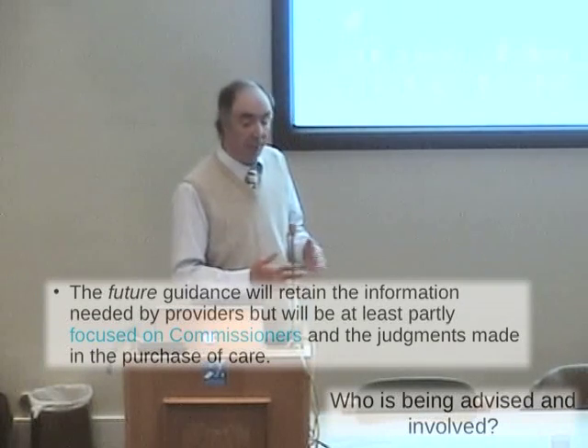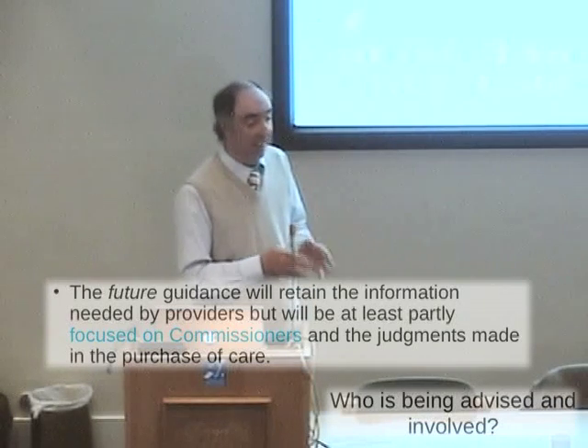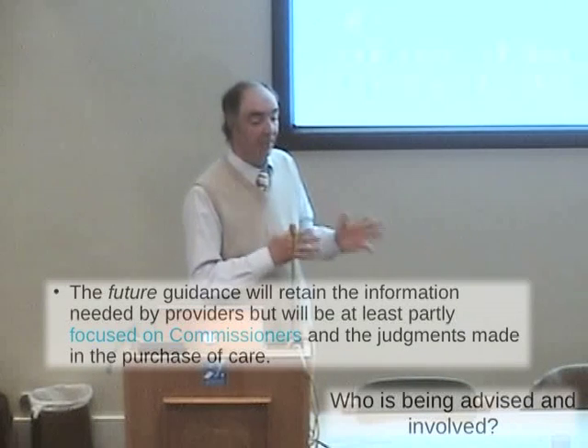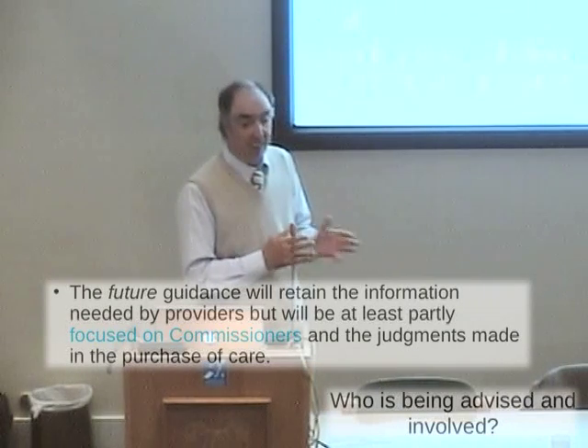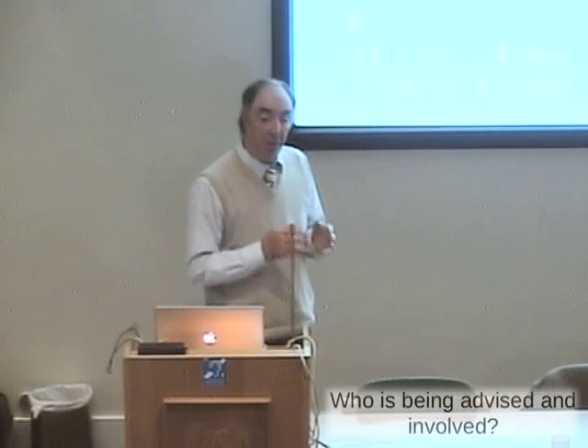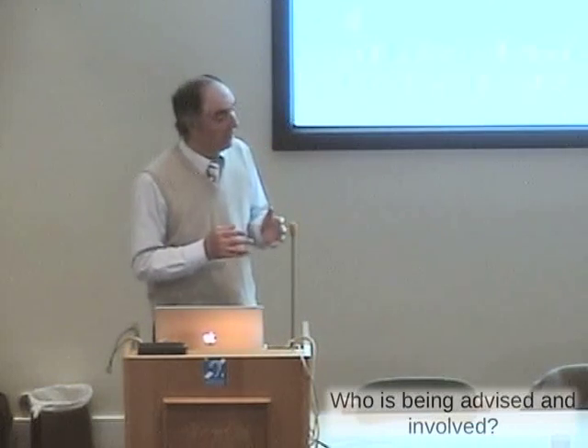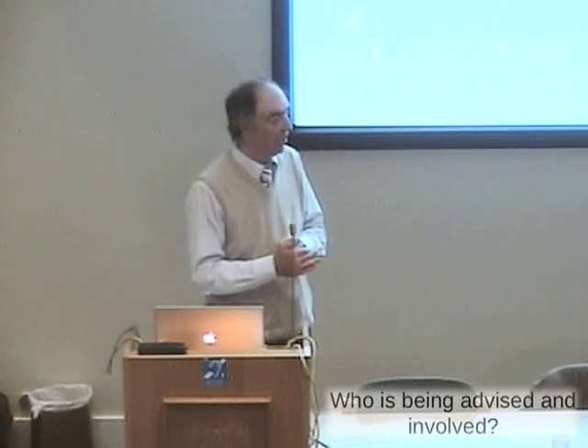The future guidance will retain the information the Department of Health knows you all value. So if we're talking about HBN 6 being redrafted, advice on the specific design of rooms will still be there. It will still relate to the 1999 ionising radiation regulations and the rest of the regulatory package, most of which is derived from the learned processes of the International Commission for Radiation Protection and institutions like this one and the Royal College of Radiologists just next door. That will still be there, but there will be a new focus on commissioners and on the commissioning process and on encouraging you toward excellence, toward keeping your costs down, toward being a very competitive institution that succeeds.